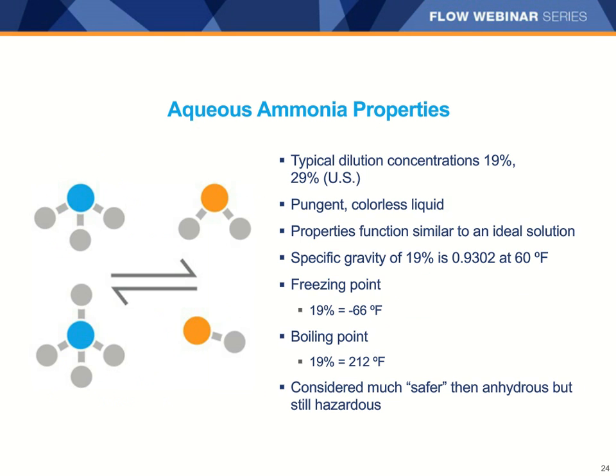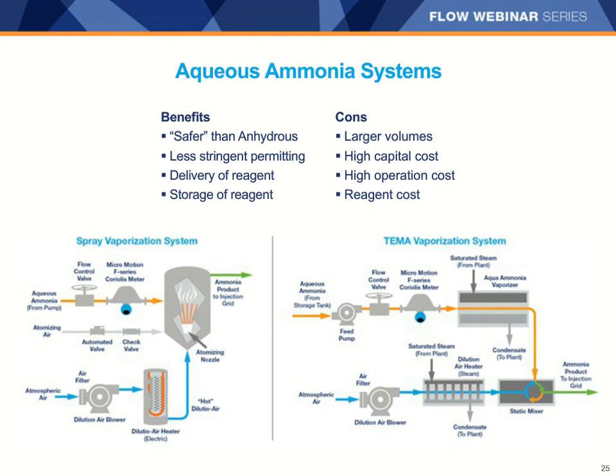Next, we have aqueous ammonia. Typical dilution concentrations in the U.S. are 19 and 29%. It is considered much safer than anhydrous, but still listed as hazardous. Here we have an aqueous ammonia system. Precise flow measurement of the aqueous ammonia going to the injection grid is important to assure that the ratio of reagent to catalyst in the SCR unit is correct. Once again, under-injection will not provide sufficient NOx scrubbing, while over-injection leads to ammonia slip.